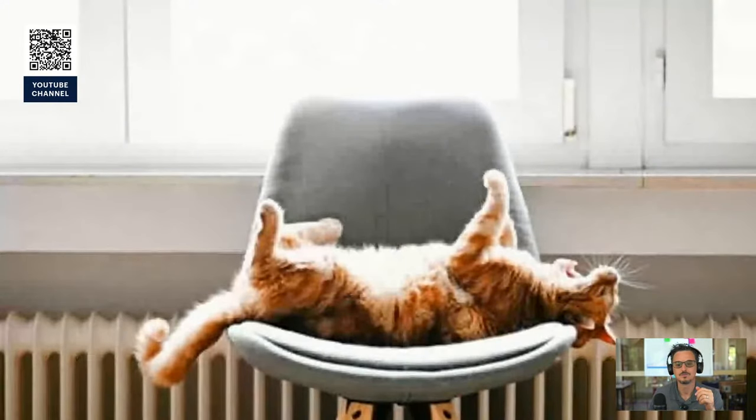So a couple more examples to look at so we can make sure we drive home the difference between sensible and latent heat. If you look at this drawing here, just look at it for a second and think, what is providing sensible heat to this space? The immediate thing is the sun coming through the windows there. That's sensible heat. The surface temperature of the inside wall is hot because it's conducting heat from the outside wall. If the radiator was on, you would have a radiator putting sensible heat into the space. And the other obvious thing would be this cat here who looks pretty comfortable. It's putting sensible heat and latent heat into the space, okay? Because most living things are going to add latent heat to the space.